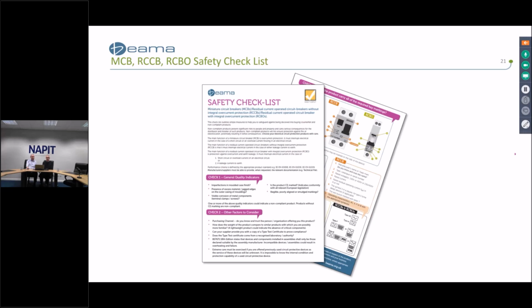So the details of it are in there, and it consists of 3 checks. Checking RCDs and MCBs, etc., for general quality indicators, other factors to consider regarding the route of purchase, the channel it is purchased from, and also the information provided on the front of the devices in terms of the characteristics of the device, what it needs to comply to and what information should be provided. So we think it's a helpful checklist.